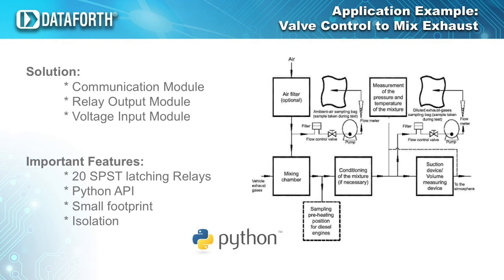Each relay can switch between 2 amps at 30 volts and 0.4 amps at 150 volts. Each channel has contact state readback to verify the physical output state. Relays can be controlled individually or in blocks and have user-configurable default output states, which are set upon power up, power loss, and module reset to ensure fail-safe operation. Other features include advanced output functions, which are detailed in the hardware user manual, user-defined logic polarity, and fast switching times. Reserve power is stored and used for predictable shutdown to user-defined relay states upon loss of module power.